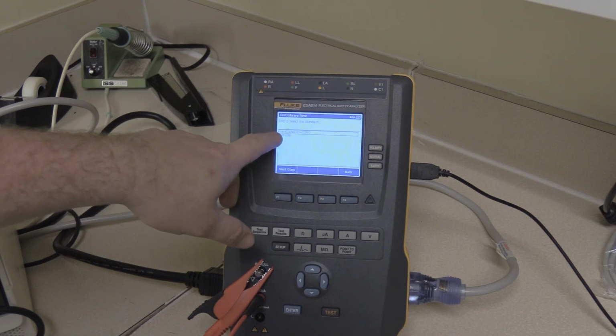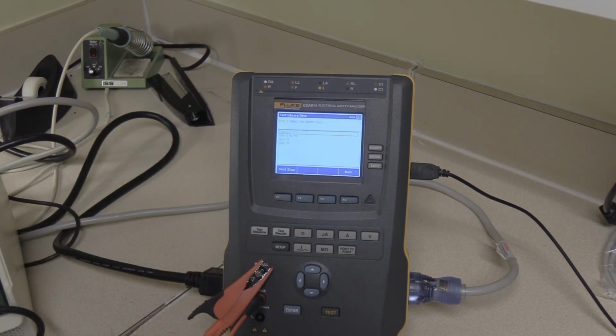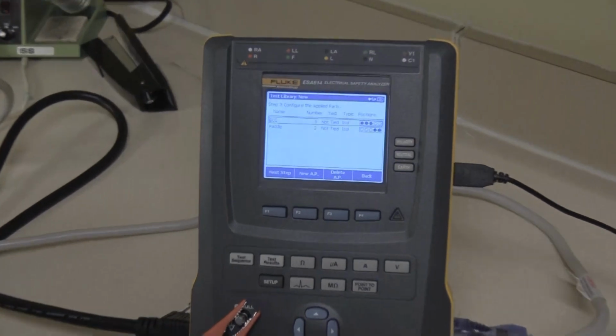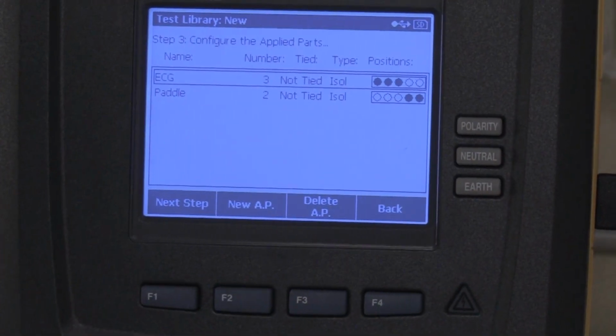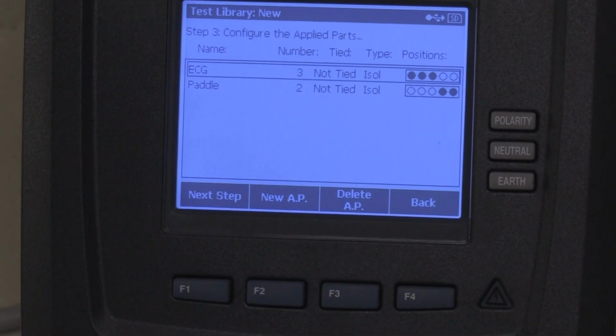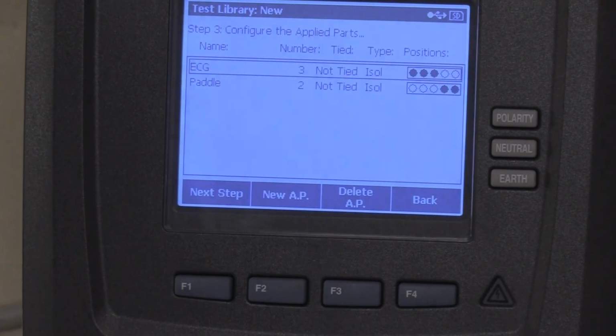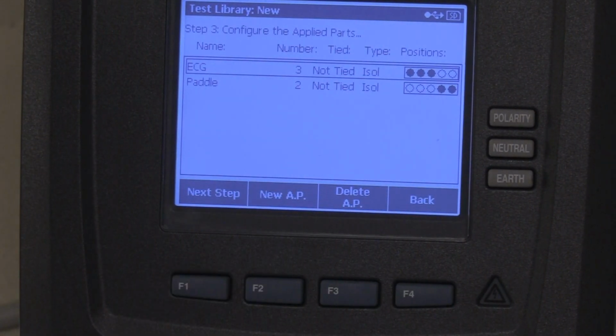So to fix this, we're going to push edit, and we're going to select the ANSI ES, that's the test we're already looking at, the next step. It's a class 1 device, we're going to go ahead and select that. And here we'll see that the ECG is going to use the first 3 ports. Scroll in here a little bit. There you go, the ECG will use the first 3 ports on the top. But you'll see here that it says that they are not tied and they are isolated.